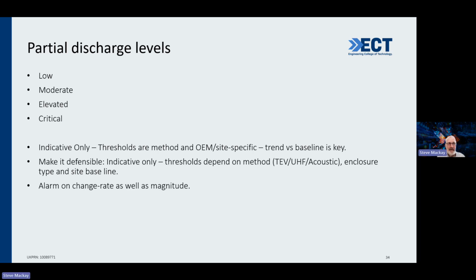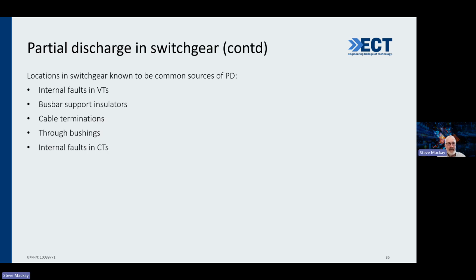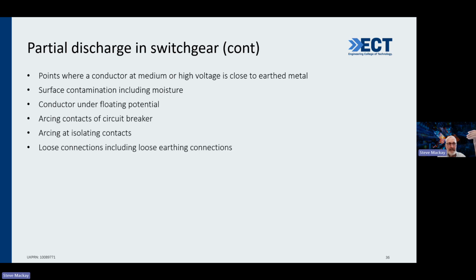So the different partial discharge levels are low, moderate, elevated, and critical, and those are all important. And these are typical locations which could have partial discharge: internal faults in your voltage transformers, bus bar support insulators, internal faults in the CTs, and through the bushings and cable terminations. Those are all good target areas.